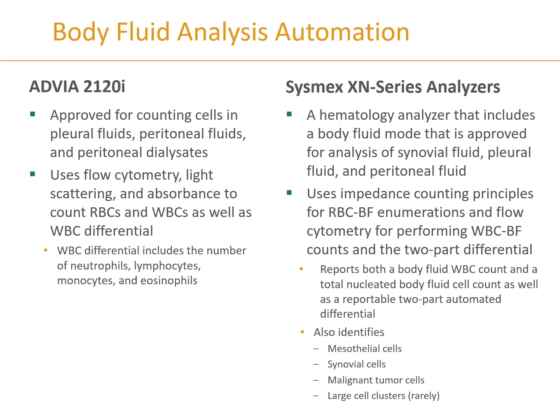The Sysmex analyzer is a hematology analyzer with a specific body fluid mode approved for synovial fluid, pleural fluid, and peritoneal fluid. It uses impedance counting for red blood cell counts and flow cytometry for white blood cell counts, further divided into a two-part differential. A notable feature is its ability to recognize abnormal cells such as mesothelial cells and malignant cells.